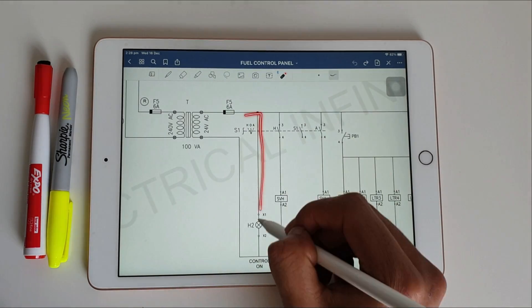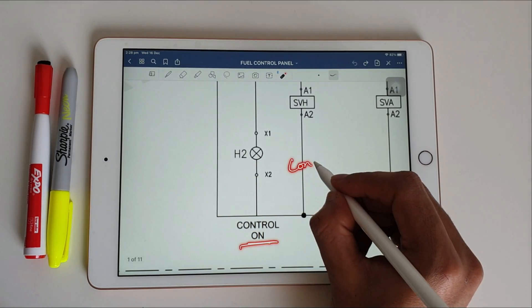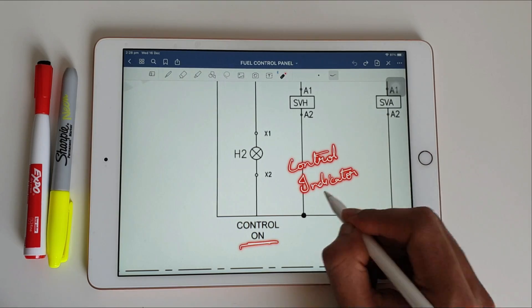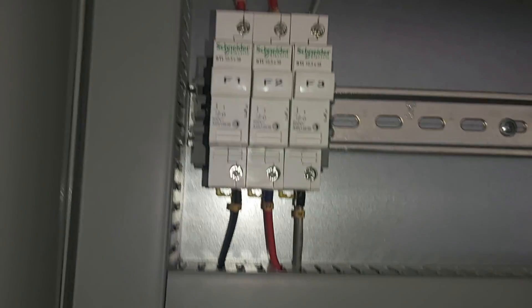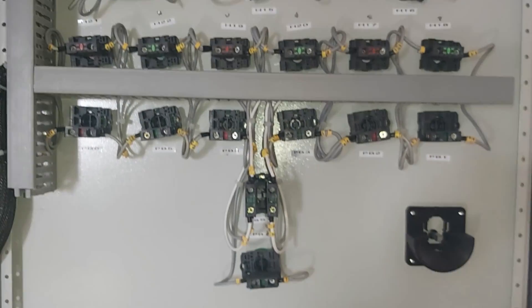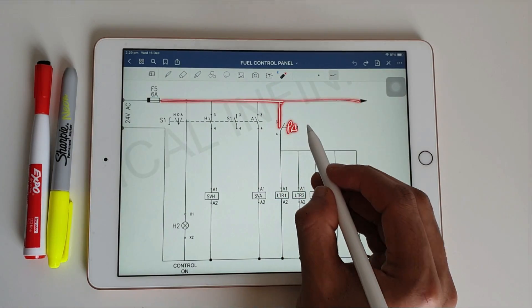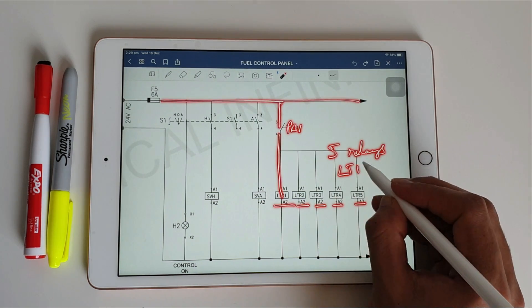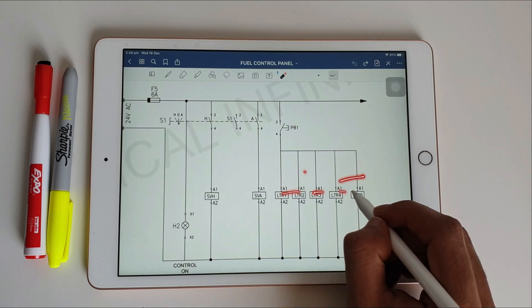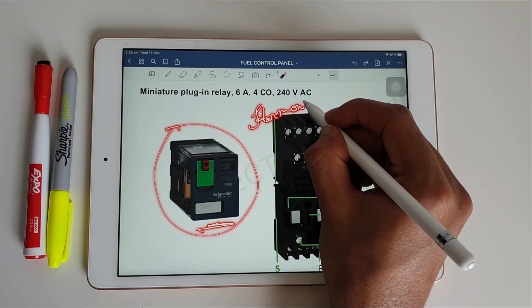This is the indicator for the control circuit — it shows whether the control circuit is working or not. From the fuse we connect to the selector switch, and from the selector switch to A1 of both contactors. From the 6 ampere fuse we also connect to a push button, and from the push button to A1 of the 5 LTR relays. These relays are used for control circuit operation and pump operations.